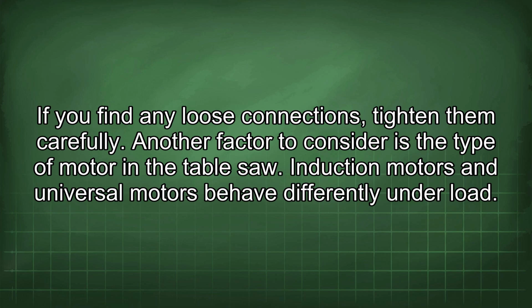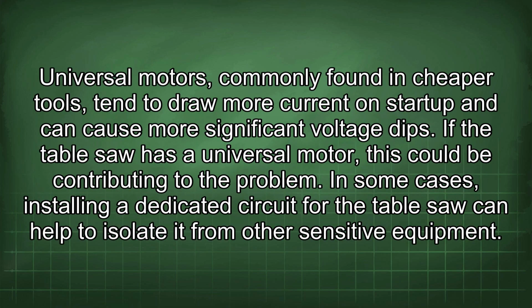Another factor to consider is the type of motor in the table saw. Induction motors and universal motors behave differently under load. Universal motors, commonly found in cheaper tools, tend to draw more current on startup and can cause more significant voltage dips. If the table saw has a universal motor, this could be contributing to the problem.